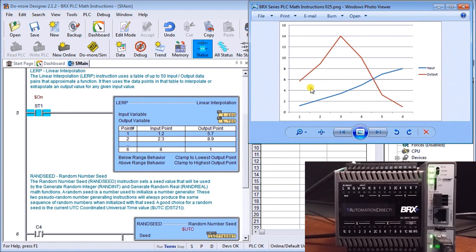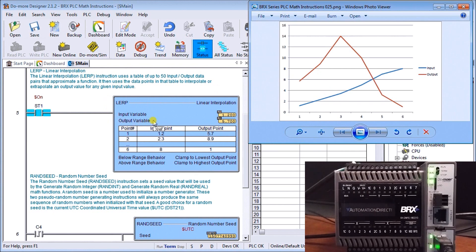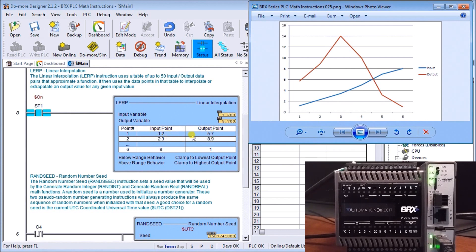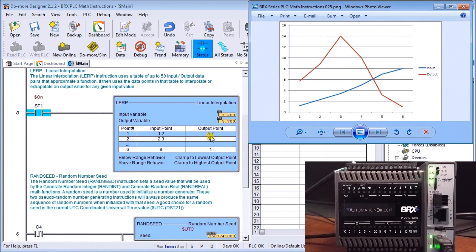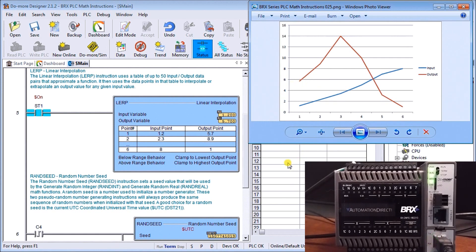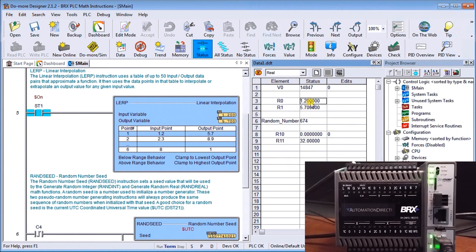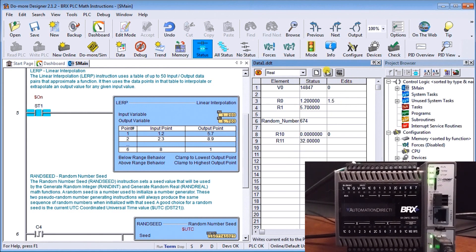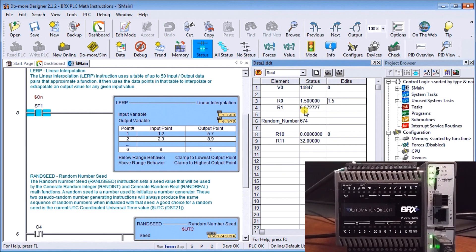I've given an input here and I get the corresponding output. Right now, if I look at my instruction, here's my input instruction. I'm putting 1.2 and I'm getting 5.7, which corresponds to my first input point. If I put in something like 1.5, we should get some number between 5.7 and 8.9, the exact interpolation between the two. Let's put in 1.5 in that value, write that into the controller, and sure enough our corresponding output is 6.57.